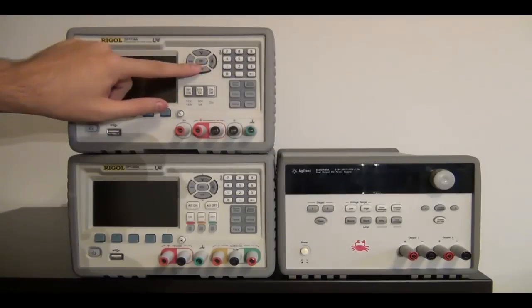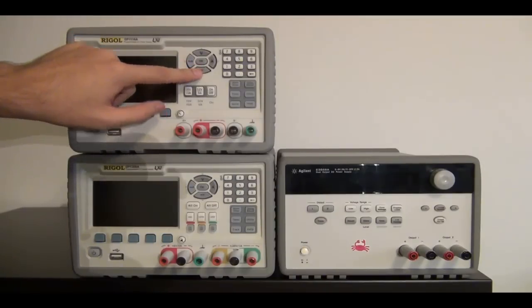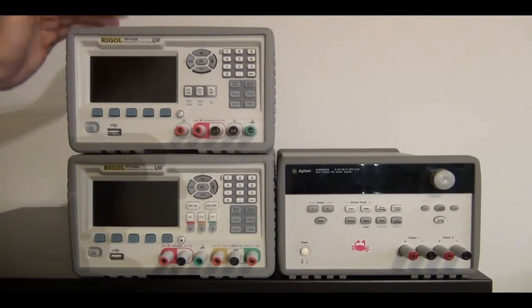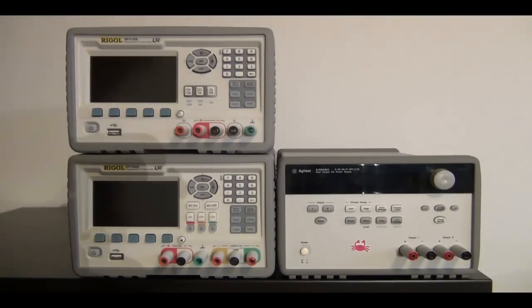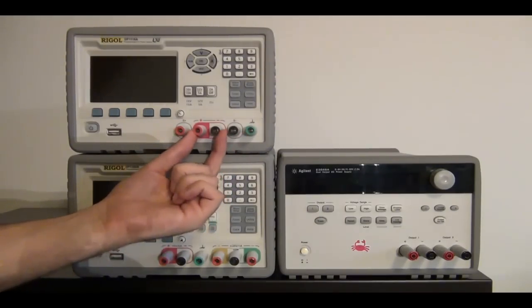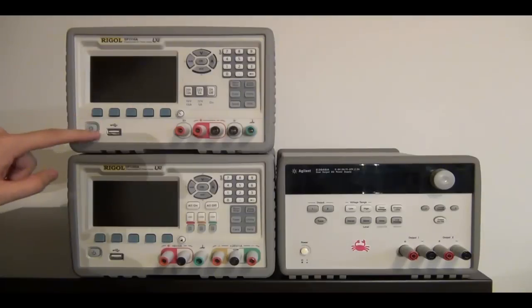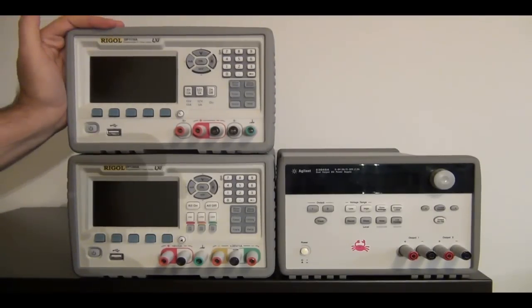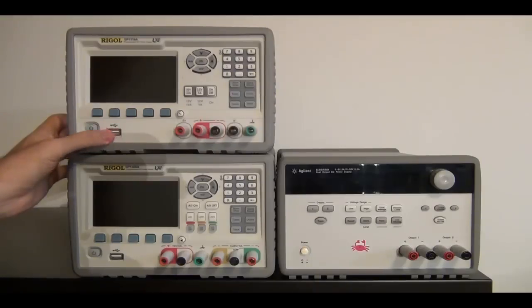They have a directional switch at the top with volts written at the top, millivolts to the bottom, milliamps to the left, and amps to the right. So you can enter a number and press the unit that you want. You don't need to necessarily select voltage or amp. It makes it much easier to enter data into the power supply. And now we have an earth ground, the green one, and we have a plus or minus sense port on the outside and plus or minus outputs here. And of course we have a USB interface in the front - another huge benefit if you need to give this guy a spreadsheet of voltages that you'd like it to go through. It's just a huge advantage having a USB where you can get data into the power supply and get data out of the power supply.